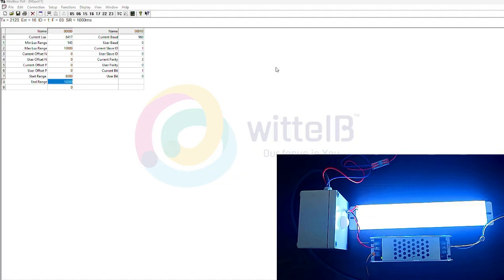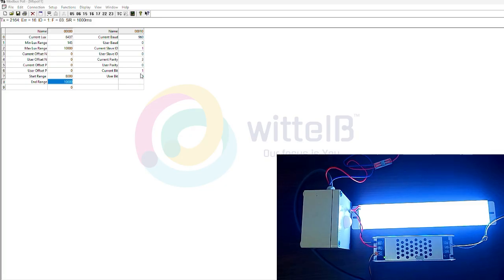In a production line, LEDs are used to illuminate the product for camera inspection, where it needs stable light. Over time, sometimes the LED loses brightness. If the voltage is suddenly increased, it can damage the remaining LEDs. So in that specific area, this lux sensor controls the driver by slowly increasing the voltage until the current lux reaches the required starting and ending range. The voltage stops increasing automatically when the current lux matches the range. So this helps keep the LED light stable.